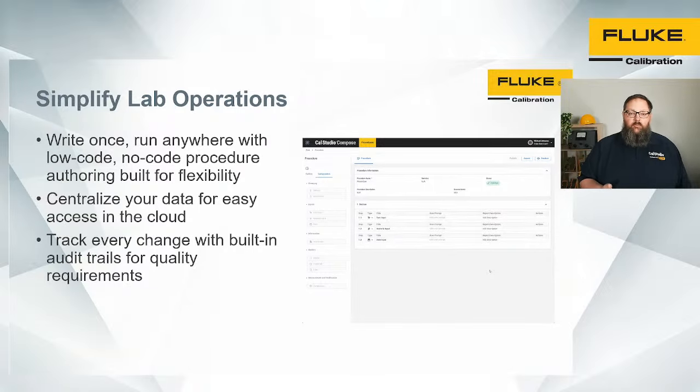I mentioned the procedure authoring, and one of the key differences here is when you think about a procedure in something like MetCal or even in some other systems, it's very much a singular entity that contains all sorts of information. It contains how we selected those test points, what those test points are, what the tolerances for those are, what the uncertainty of the standards I'm using is, and all of that is in this singular package. With Qubit a few years ago, we started thinking about how to separate those things out into individual data entities and then combining them dynamically.